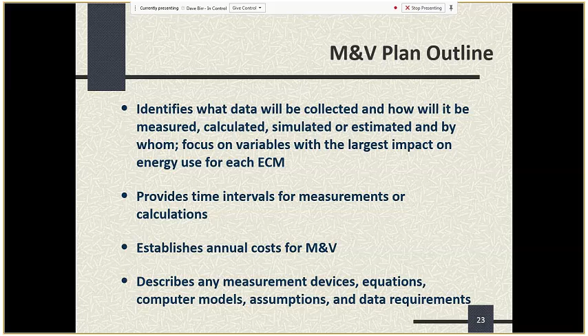It provides time intervals for measurements where you're doing trend logging, for example, of the VFDs on the ventilation fans. That trend log data is very critical to finding out what's actually happening with the speed of those fans over time. It also lays out the budget for M&V, what equations, models and assumptions are being used, and what data is required to complete the M&V plan.